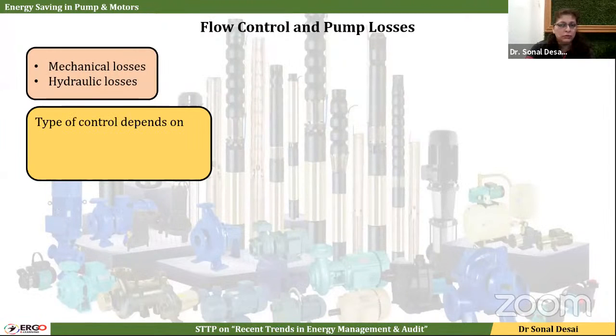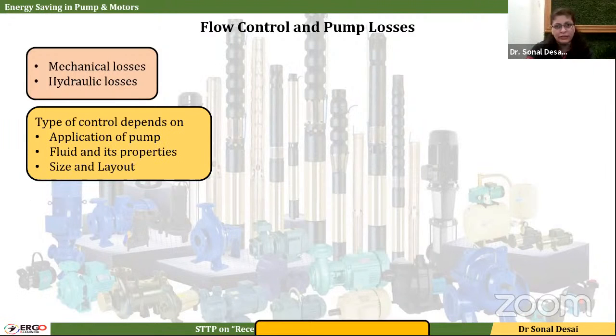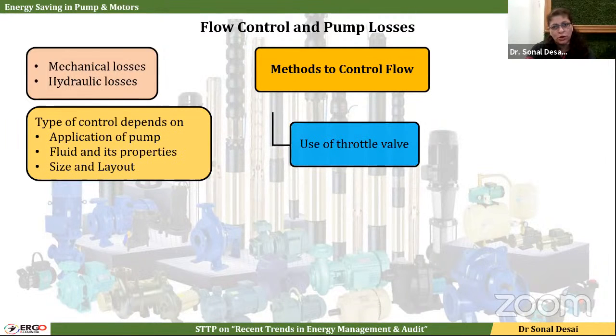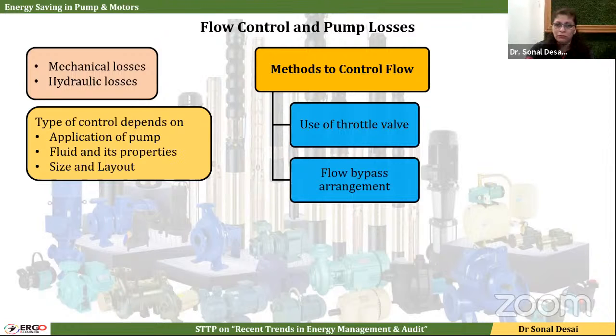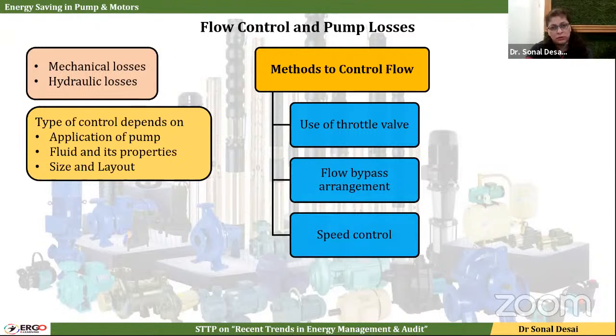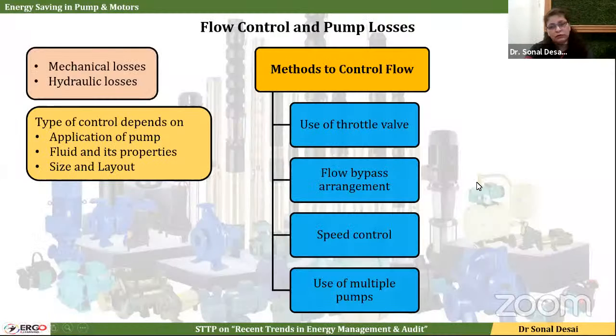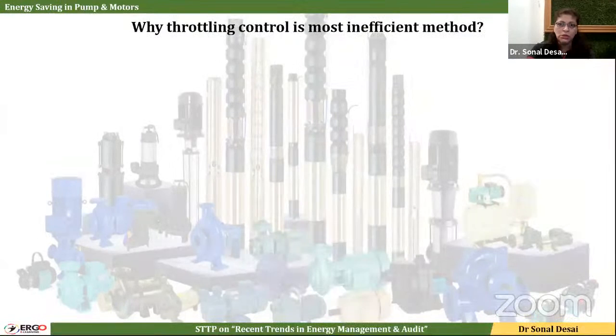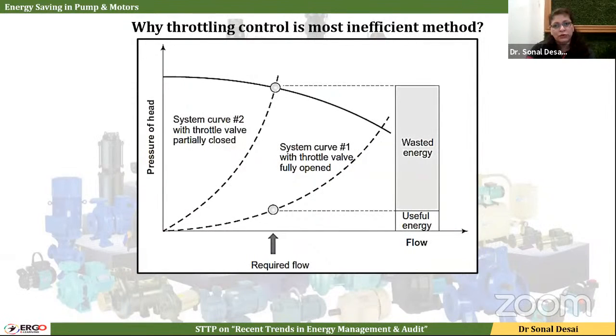That is basically controlled by different devices, and it will create either mechanical loss or hydraulic losses. The types of controllers and their effect on the pump working system are discussed in the subsequent slides. Normally, a throttle valve is used, which is the most inefficient method. In some cases, the flow bypass method is used, wherein rather than routing the flow in the required piping, flow is diverted to some bypass line and then it goes back. The latter options are somewhat viable, but with the first two options we are putting our leg on the edge and reducing the performance by increasing running cost. Why throttling is very inefficient is shown in the slide of the pressure versus flow diagram.